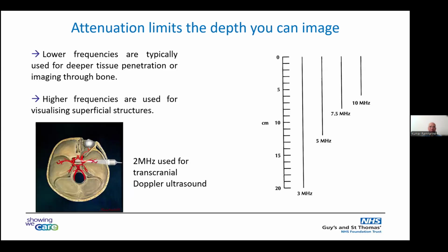There are two important characteristics between attenuation and the frequency. High frequency ultrasound will be attenuated more than low frequency ultrasound. So there's always this trade-off between high frequency and high resolution, because high frequency ultrasound will have a small wavelength, therefore you will have a higher resolution image. Because you have more attenuation, you're not going to be able to visualize deep tissues. So the trade-off is between high resolution or high penetration depth. If you want to penetrate deeper into the tissue, say you're looking at a liver, then you want to have a low frequency transducer, but you sacrifice the visual quality, the resolution capabilities of the image.